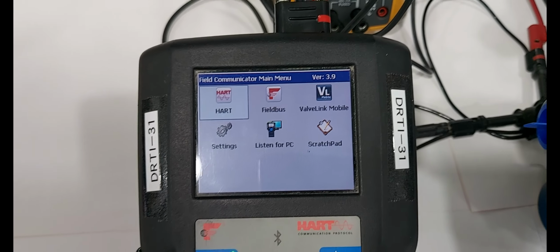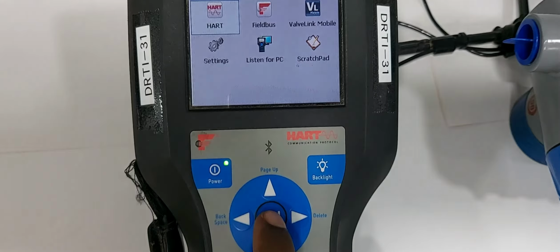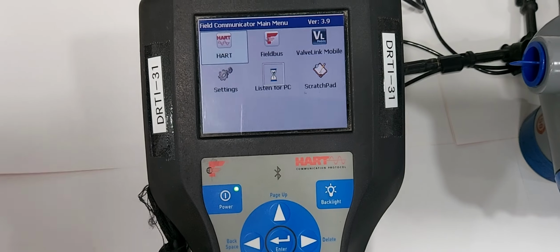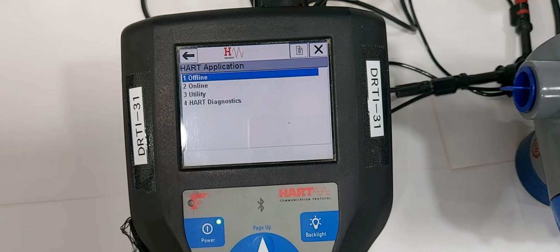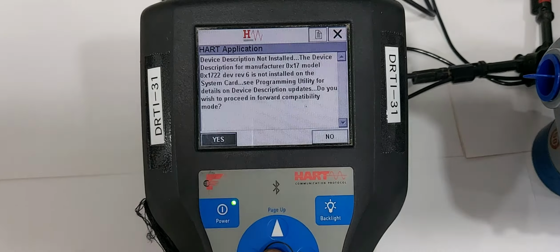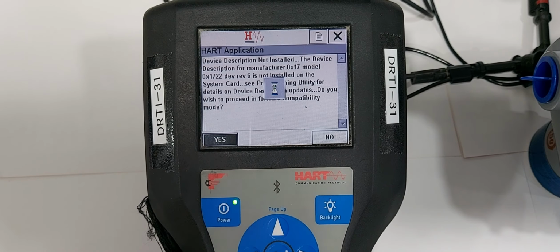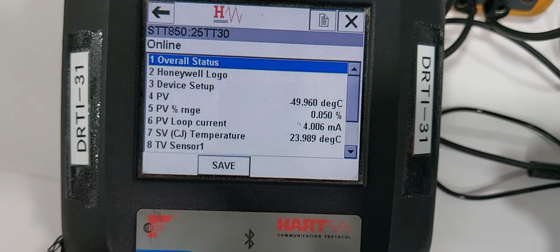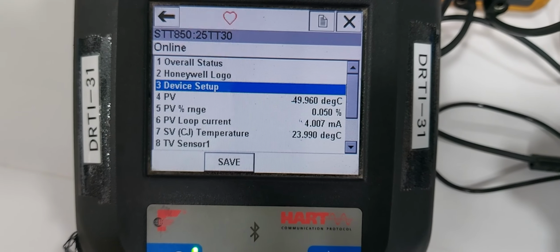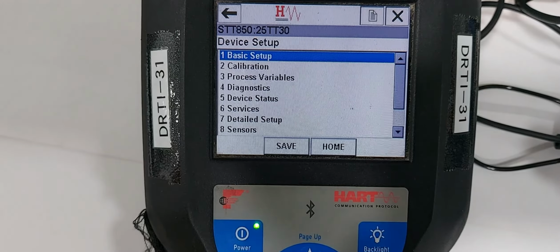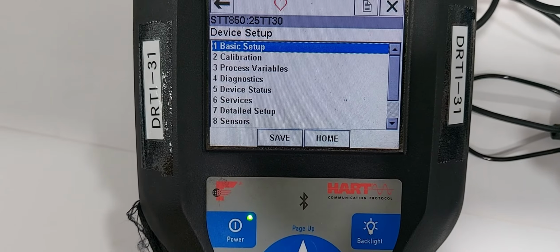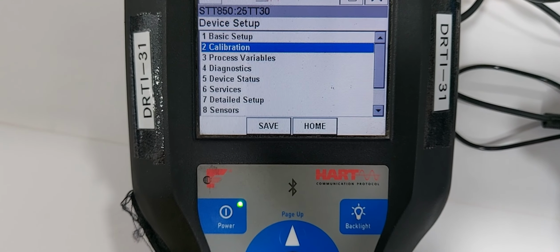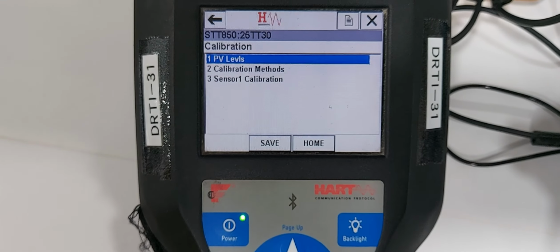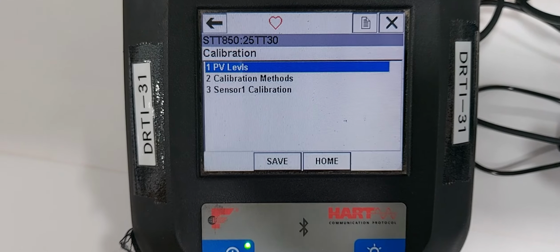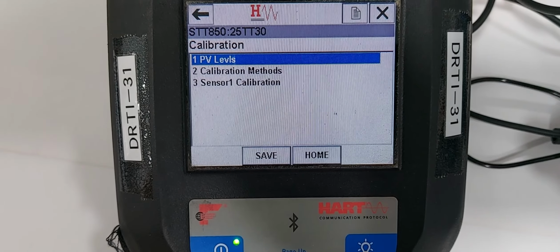First select the HART menu. This is the online menu. Select Device setup, number 3. In the device setup menu, first we are selecting the calibration menu, number 2. The calibration menu has 3 options: PV level options, calibration method and sensor calibration.